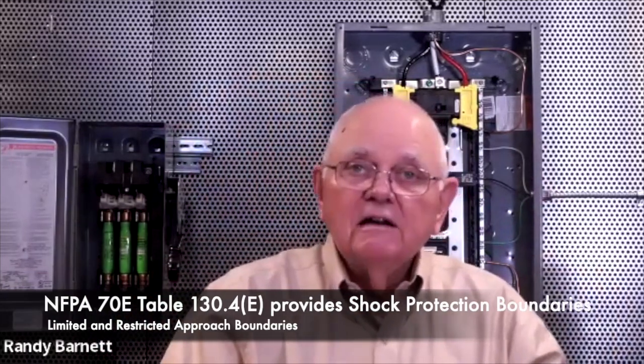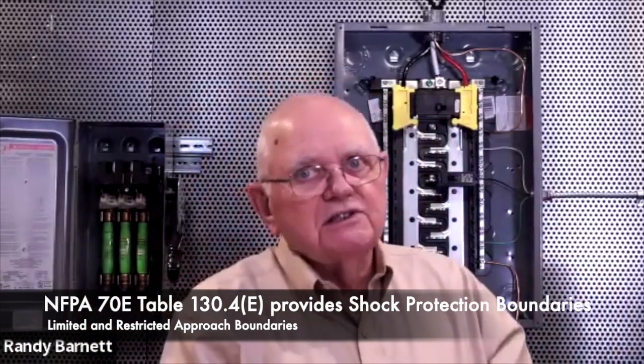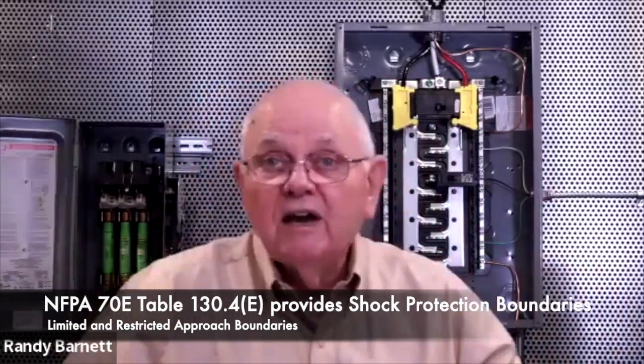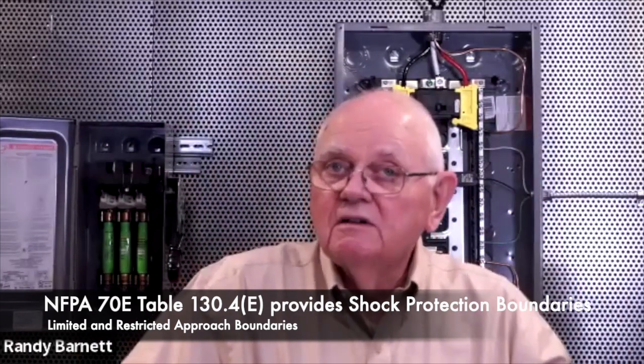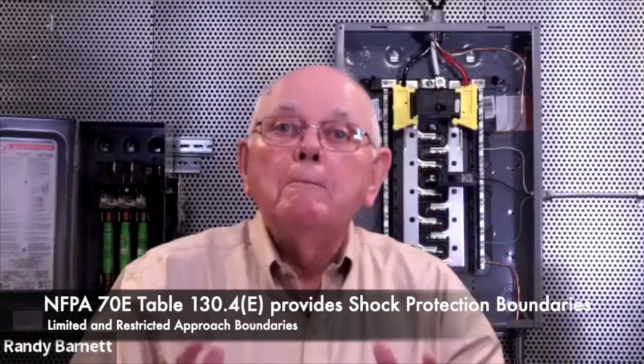Okay? So if I go to table 130.4E, then table A is for AC systems, table B is for DC systems. So table 130.4E in the NFPA 70E standards gives me the limited and restricted approach boundaries.